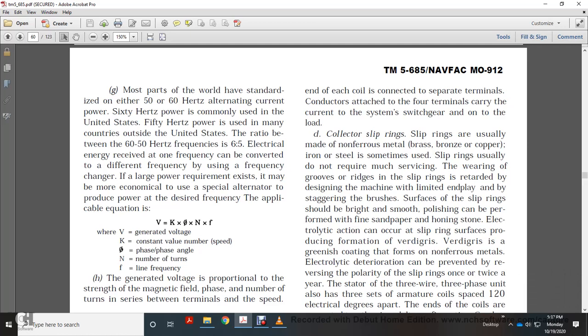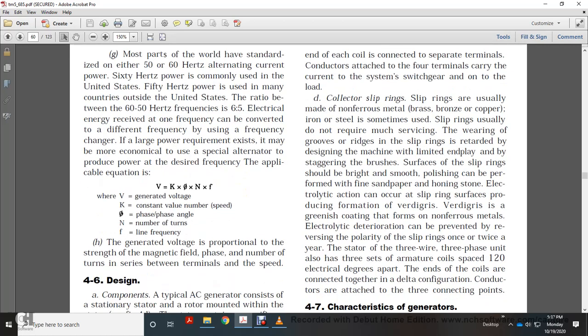Polishing can be performed with fine sandpaper or honing stone. Electrolytic action can occur on the slip ring surface, producing verdigris, a green tarnish coating, which forms on non-ferrous metal. Electrolytic deterioration can be prevented by reversing the polarity of the slip rings once or twice a year.